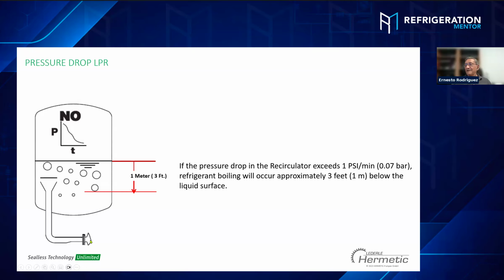For example, I have a sample from one contractor starting a system. They called me, brand new pump, and the pump had cavitated. I said, what are you doing? They said, I'm starting the system. Okay, now this is my capacity, I need to go to the temperature of the system today. I said, okay, wait. You need to be careful. You need to go 1 psi per minute. You're going to take maybe an extra 2 or 3 hours. You need to go step by step, because you're going to damage the pump.